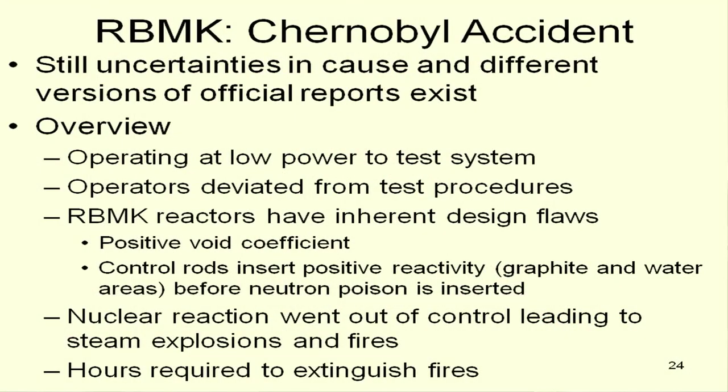There were 18 of these built. Got myself a typo there. And this is the Chernobyl reactor. By design, this reactor had some problems. First, it had a positive void coefficient in some places, which means if you start boiling it, reactivity gets worse. At the outset it didn't have any real containment, more like the secondary containment on BWRs, and after TMI, just partial containment. For this accident, even after these many years, there's still some uncertainty. There's been more than one official report, and they like to disagree, so that's a problem.